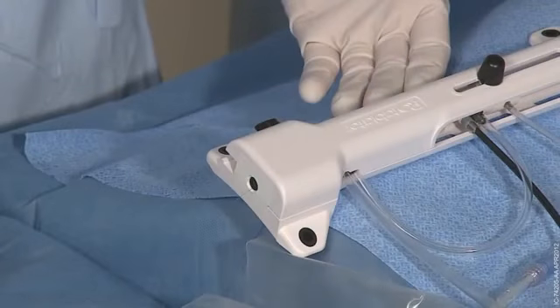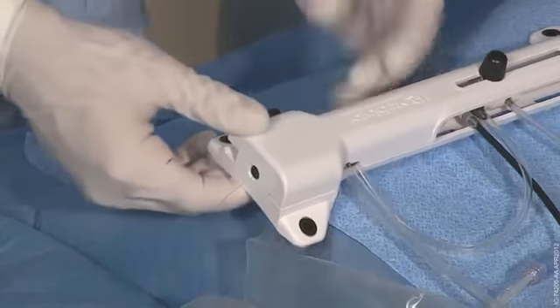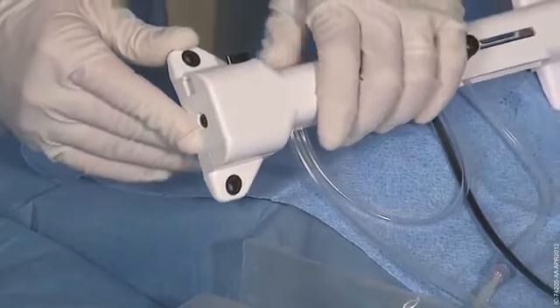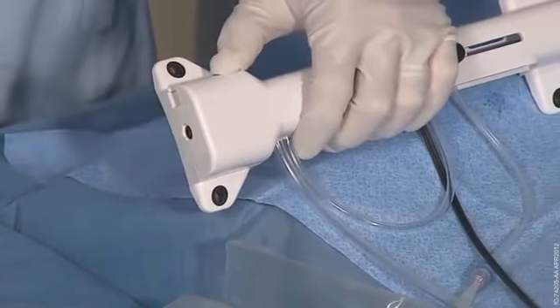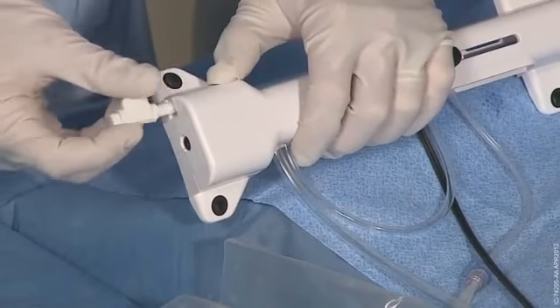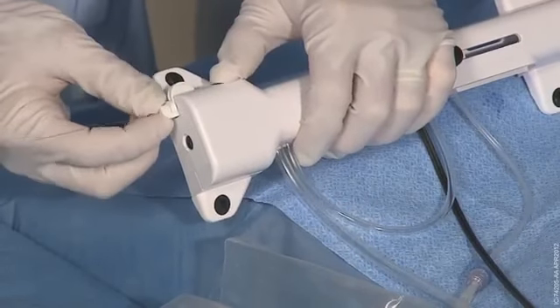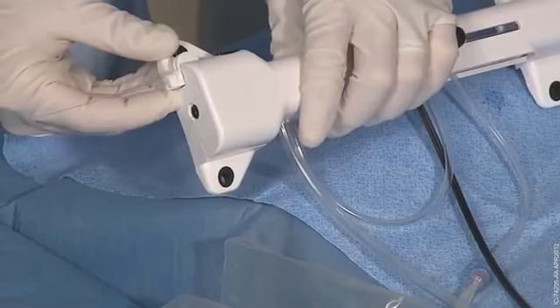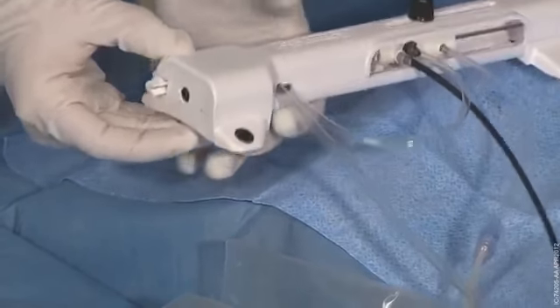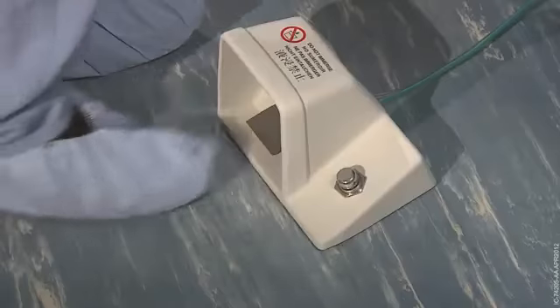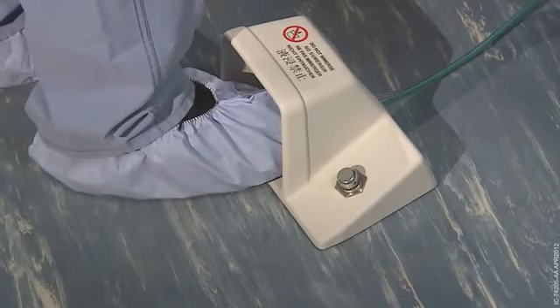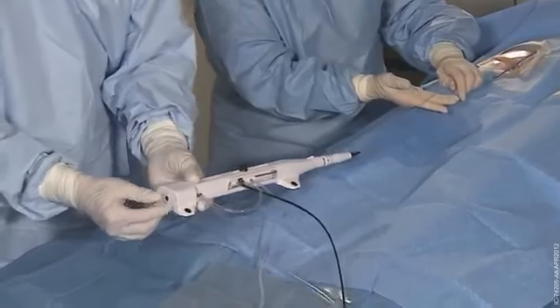You may also utilize the docking port in the advancer. Do this by ensuring the torquer is at the end of the guide wire. Push the brake defeat button and insert the wire clip torquer into the docking port. This eliminates the need to hold the brake defeat button manually during removal. Step on the foot pedal and remove the burr catheter while maintaining wire position in the patient.